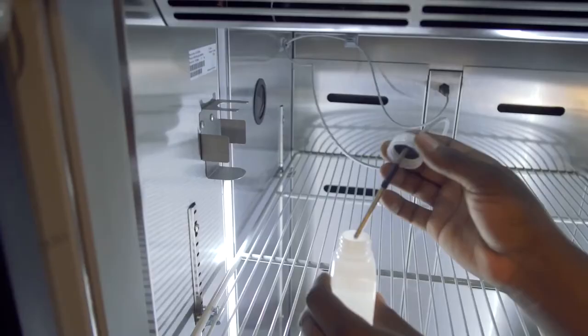For freezers, an inch and three quarters of glycerin and an inch and one quarter of water should be used, creating a 60-40 glycerin to water mixture.